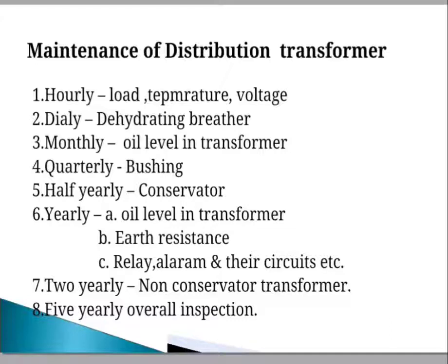We have to carry out the maintenance on a yearly basis. In that yearly basis, we have to check the oil in the transformer. In that, we have to check the dielectric strength of the oil, the water content, and the acidity and sludge test on the oil, because the oil plays a very important role in the transformer for cooling purposes as well as insulation purposes.